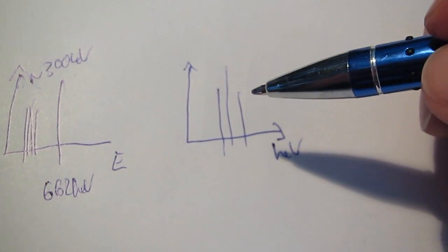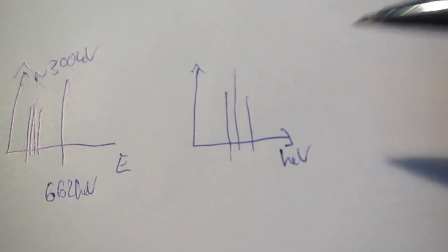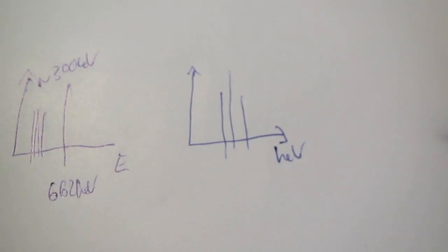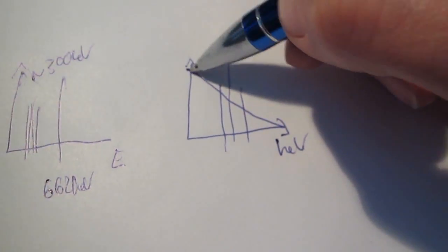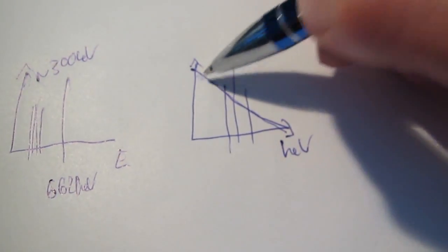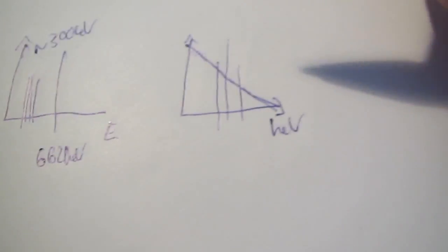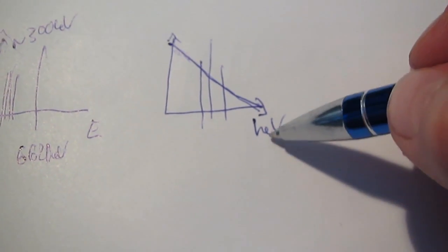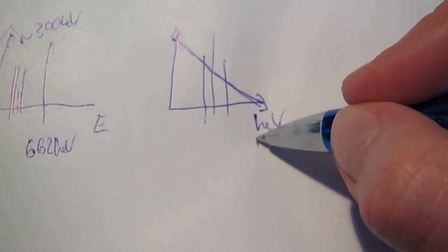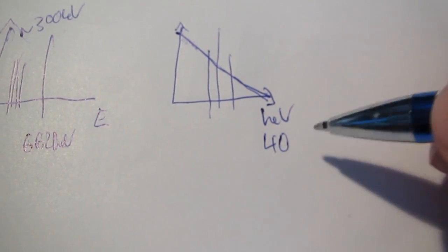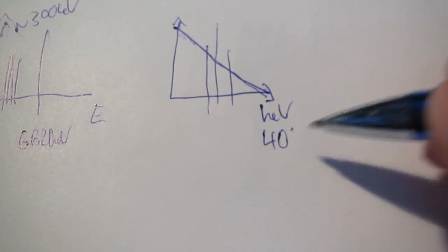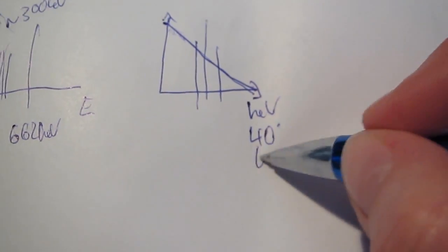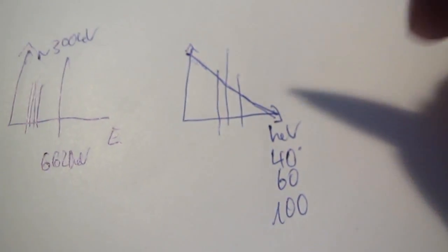The most stuff that occurs in a conventional tube, in a conventional tungsten anode tube which I'm going to use, is Bremsstrahlung, which is a continuous spectrum that runs in a linear fashion with most of the photons being emitted in a lower energy range and least of them in a higher energy range, with the maximum photon energy being your anode voltage pretty much. So it could be 40 keV if you set the anode voltage to 40 kV, 60 kV, 100 kV, whatever you set the tube to.